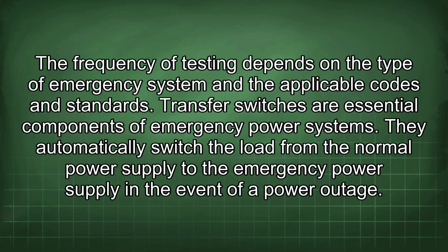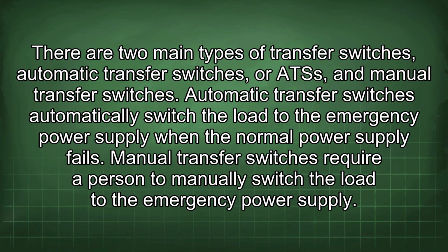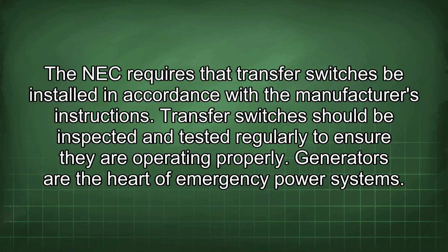Transfer switches are essential components of emergency power systems. They automatically switch the load from the normal power supply to the emergency power supply in the event of a power outage. There are two main types of transfer switches: automatic transfer switches, or ATSs, and manual transfer switches. Automatic transfer switches automatically switch the load to the emergency power supply when the normal power supply fails. Manual transfer switches require a person to manually switch the load to the emergency power supply. The NEC requires that transfer switches be installed in accordance with the manufacturer's instructions. Transfer switches should be inspected and tested regularly to ensure they are operating properly.